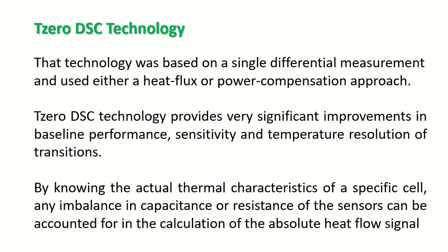The performance limitations of those early technologies could be seen in baselines that were neither flat nor very reproducible, and in peak widths that were much greater than expected from the melting of pure metals.